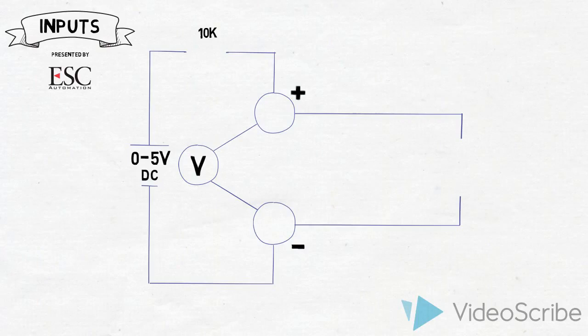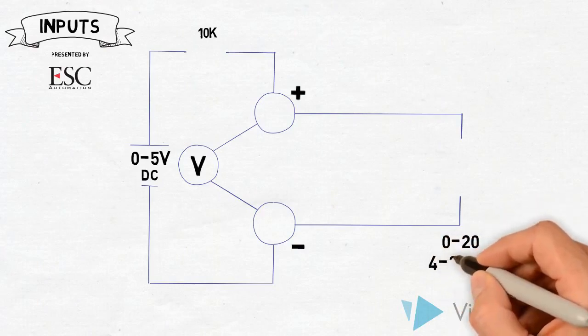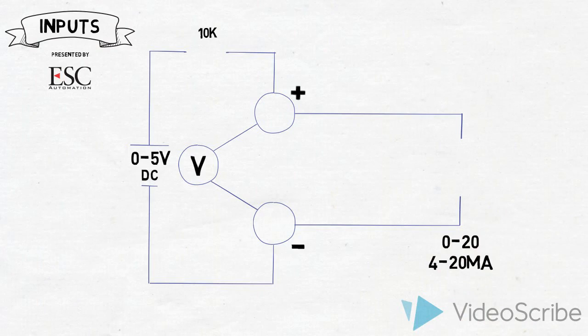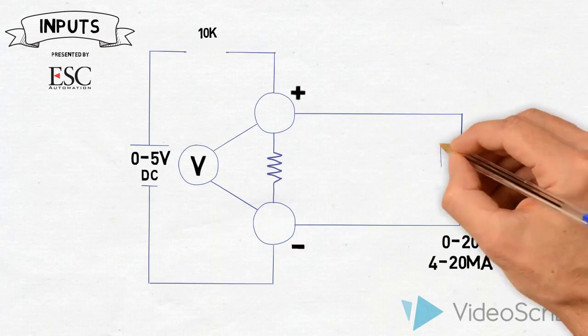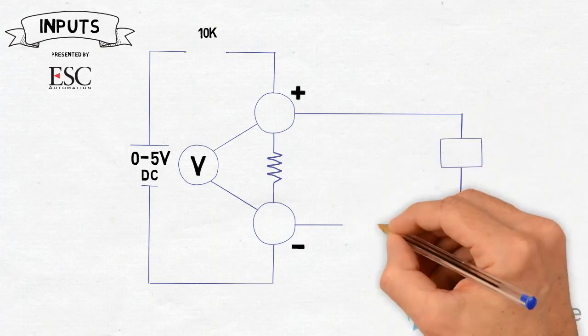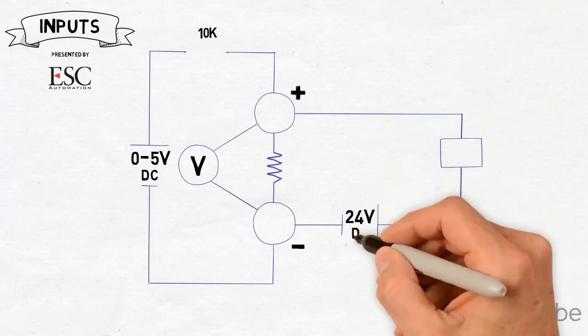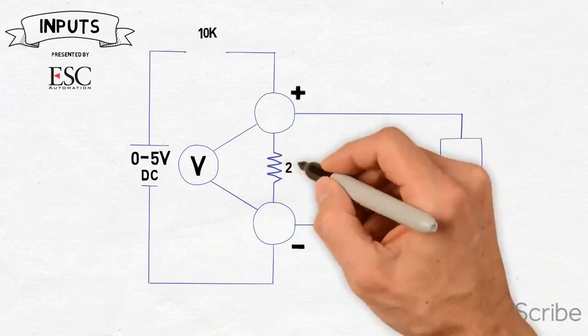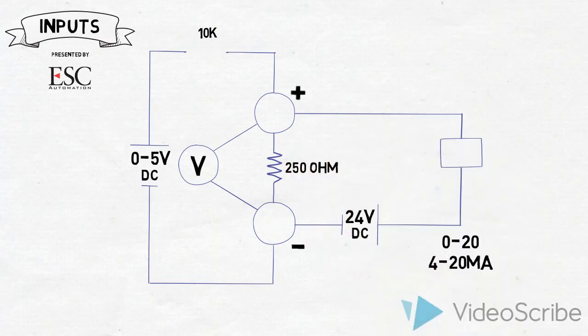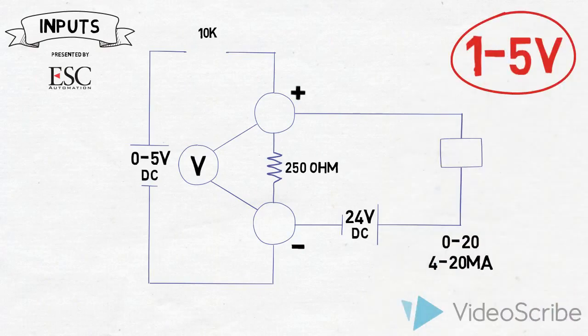The next input is a device that provides a 4 to 20 milliamp signal—sometimes 0 to 20 or 4 to 20 milliamps. When you set the panel to 4 to 20 milliamps on the dip switch, the panel puts in a 250 ohm resistor. If you have a device with a separate power supply, usually a 24 volt DC power supply, you get a voltage reading across this 250 ohm resistor. Using Ohm's law, if you put 4 milliamps through 250 ohms, you get 1 volt. If you put 20 milliamps through 250 ohms, you get 5 volts. The voltmeter reads 0 to 5 volts.